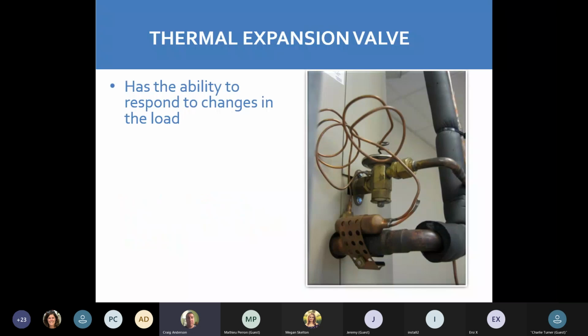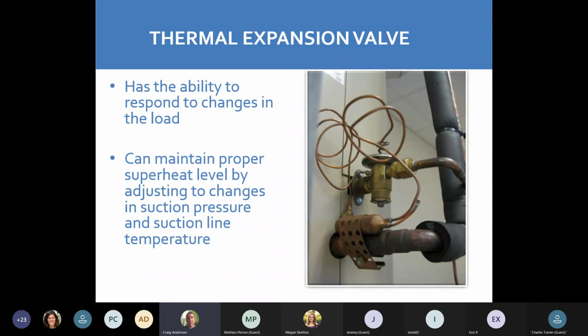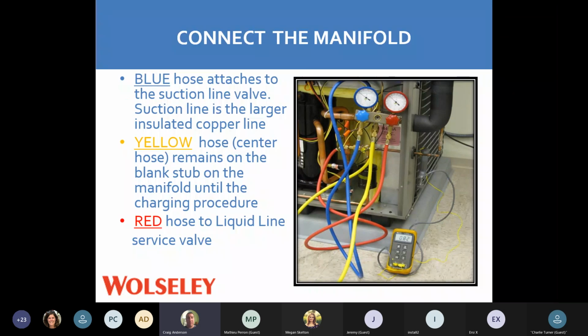So thermal expansion valve, the ability to respond to the change in the load. So it's responding to the change of the load to maintain a proper superheat on your suction pressure. So it's taking your suction line temperature to change that TX valve, whether it's opening or closing, to put the freon through your lines. Typical hookup, your blue, your yellow, your red. Your yellow's going to your charging tank. Blue's going to the larger one, which is your suction line, and red's going to your liquid line, which is the smaller one.